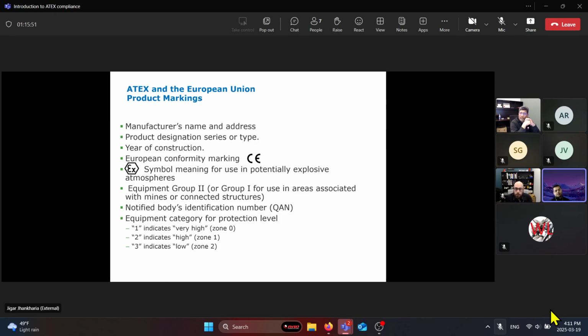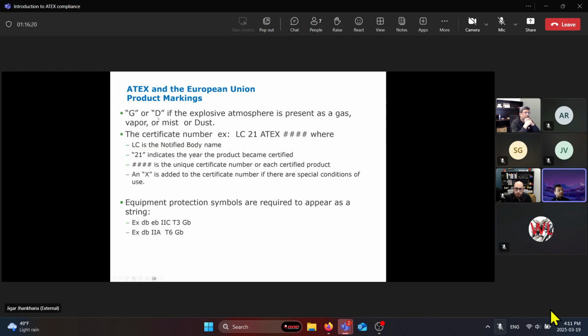And then for IECEx, it would be a bit different. It would state Ex, the method of protection. For example, in this case, if it's Ex eb for increased safety for zone 1, then it would state Ex eb, the gas group, and then temperature classification, and then Ga, Gb, or Gc. So if it's eb, then the equivalent is Gb for category 2. If it's ec, then the equivalent is Gc for category 3. And then the G or D for dust basically states the gas or dust requirements that the product is certified for.